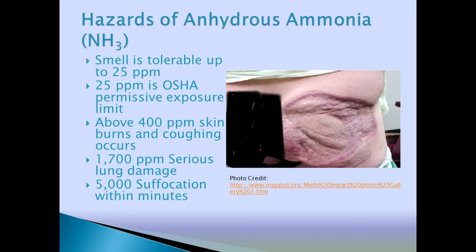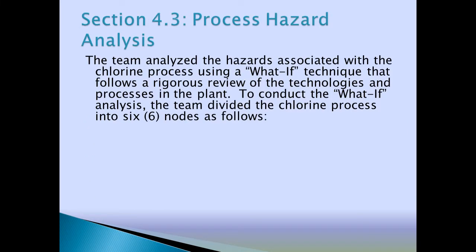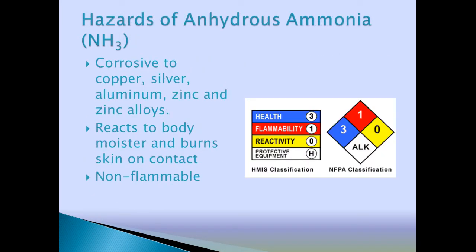At 1,700 parts per million it's serious lung damage, and at 5,000 ppm you can have suffocation within minutes of being in the presence of anhydrous ammonia. So if there's a bulk tank at your facility with anhydrous ammonia, chances are you're right at that 5,000 range, possibly. A 2,000 to 3,000 gallon tank would be on the lower side.